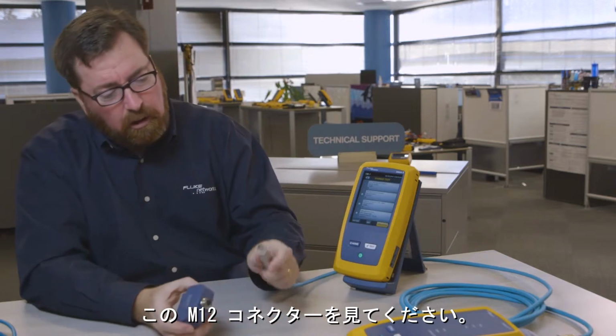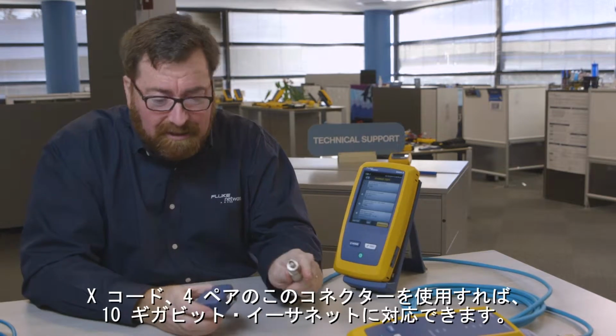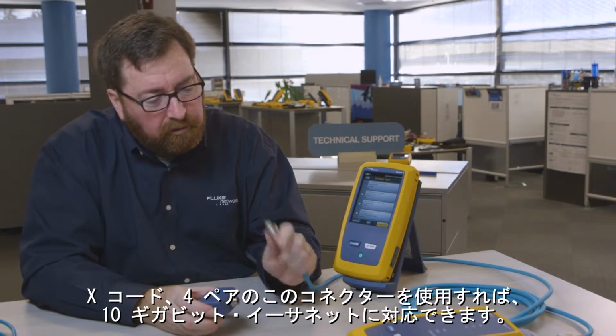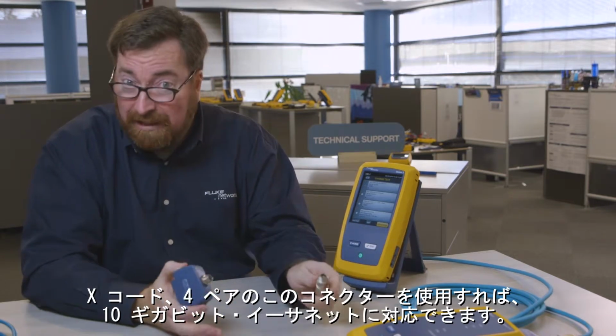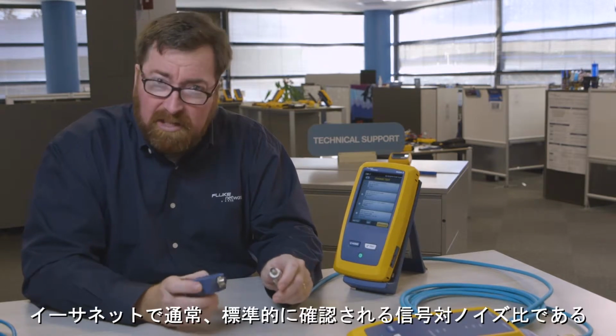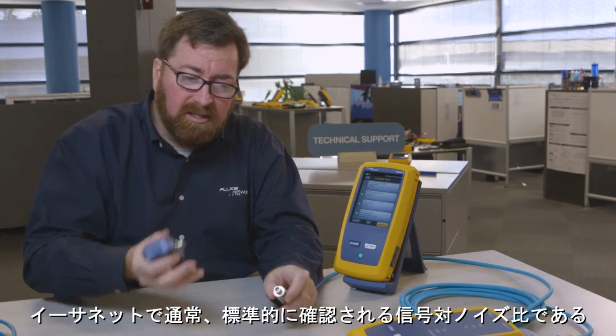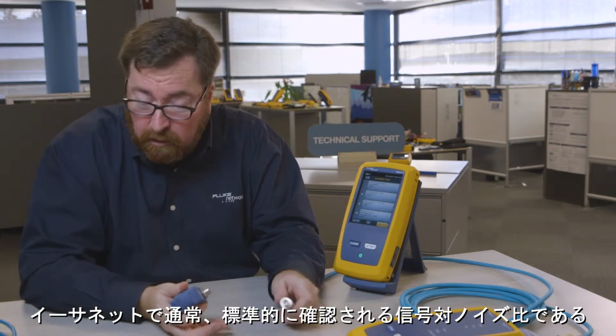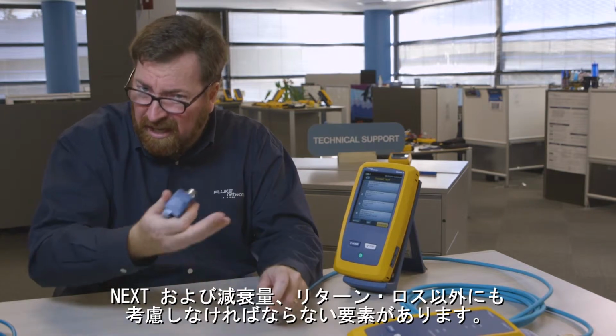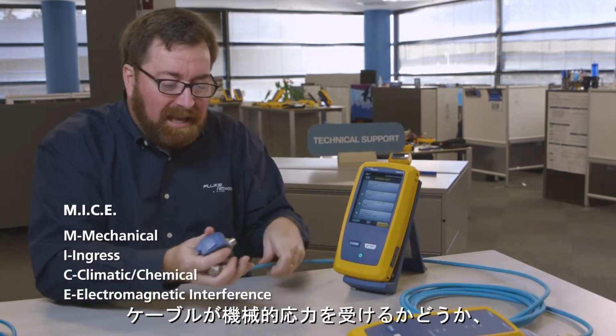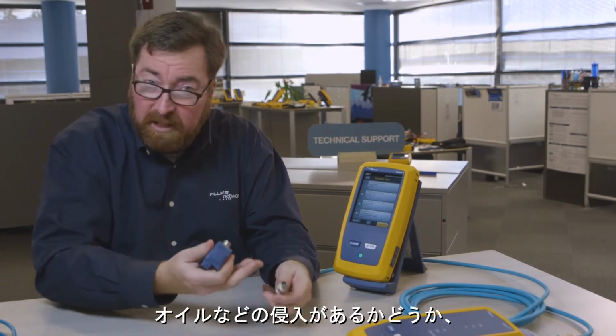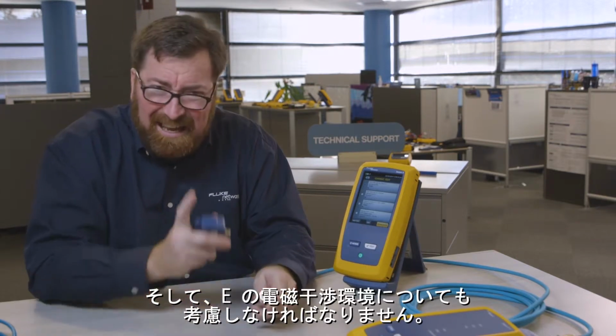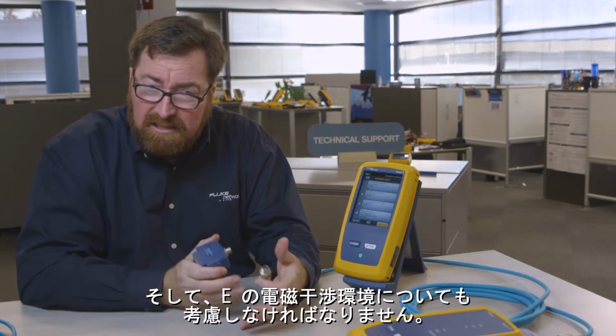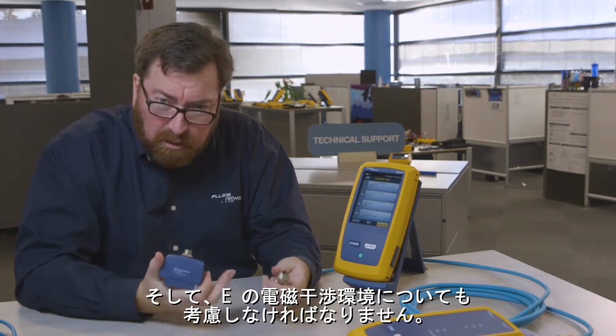And so if we look at this M12, this is again the Xcode, so it's 4 pairs capable of supporting 10 gigabit Ethernet. We have concerns beyond the standard signal-to-noise ratio that we usually look at with Ethernet: attenuation, NEXT, and return loss. We start to worry about MICE. Mice, yes. Is there going to be mechanical stress on our cable? Is there the possibility of ingress, oil or something? And the E in MICE has to do with the electromagnetic environment.